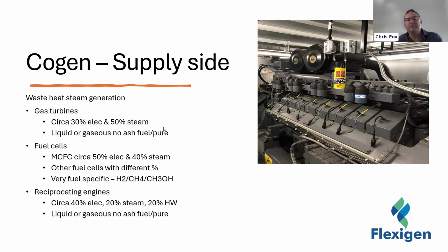So what you can do is put in a thing called a duct burner, where you just squirt more fuel into the exhaust. It burns because the exhaust is around 300-400 degrees, and it will increase the amount of steam that the HRSG produces.